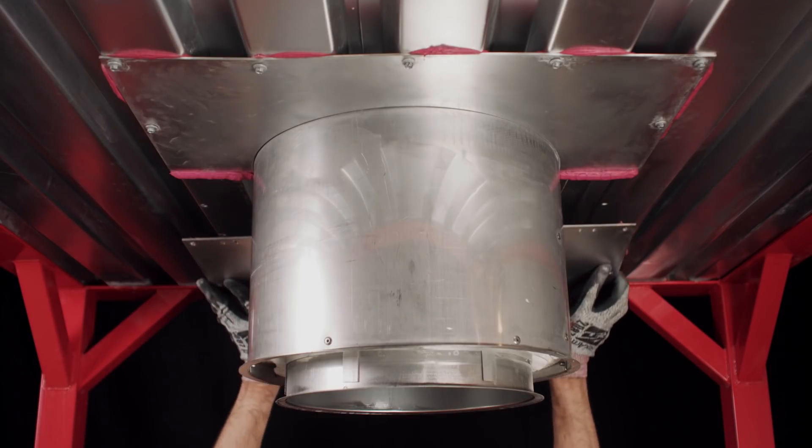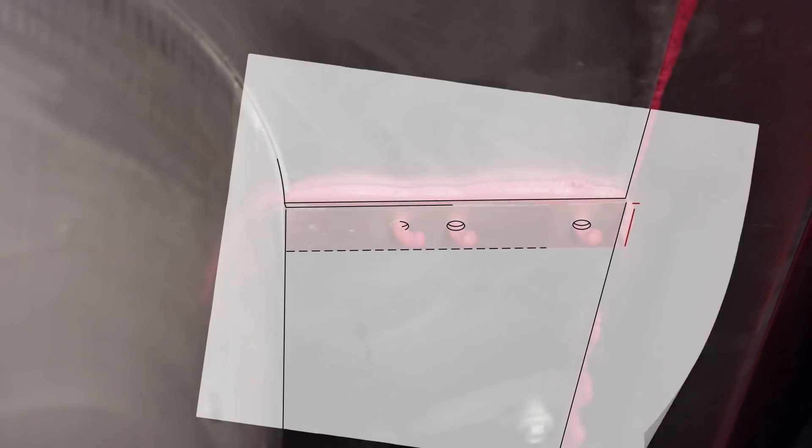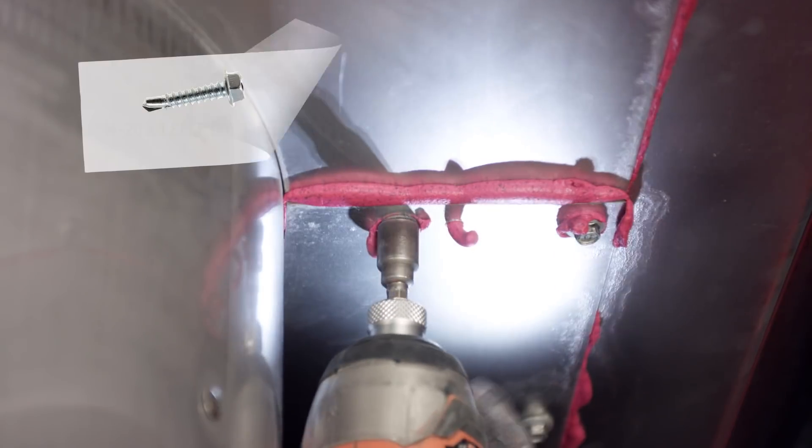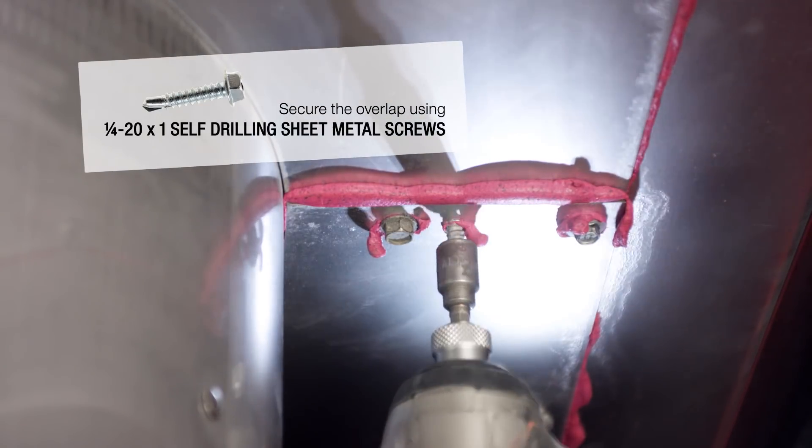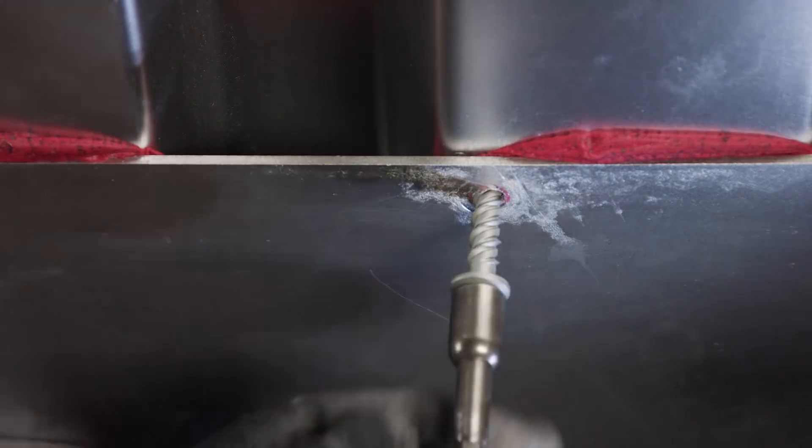Just like the first fire plate, press the second plate onto the underside of the floor with a one inch overlap so the centering holes in each plate line up. Secure the overlap using quarter-twenty by one inch self-drilling sheet metal screws and secure the outside edge using the specified fasteners.